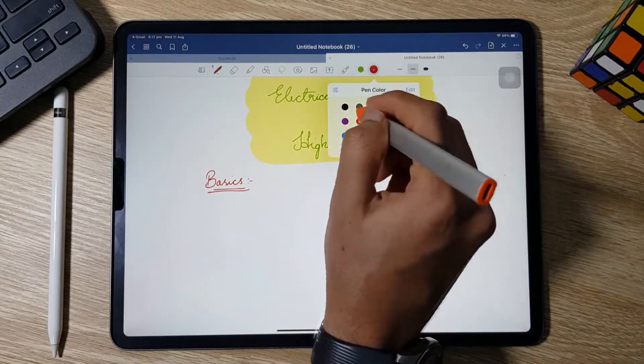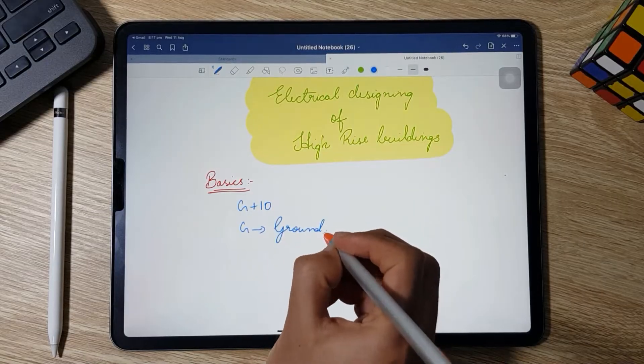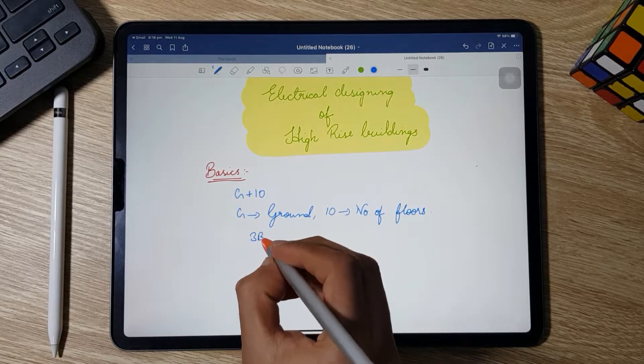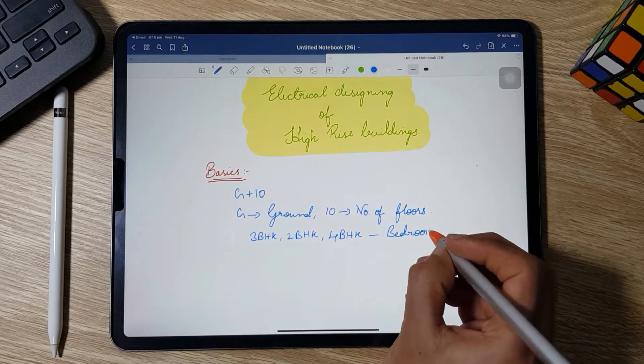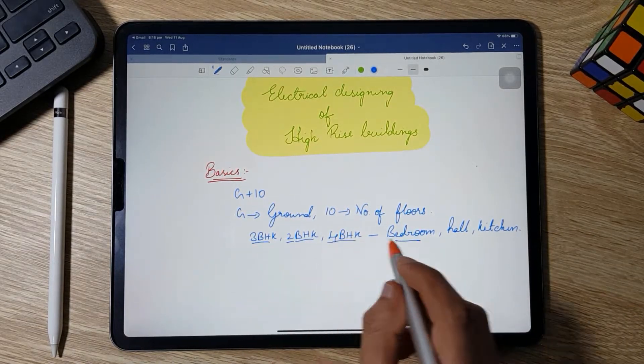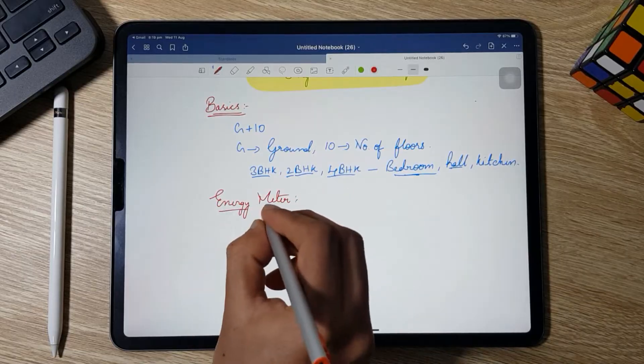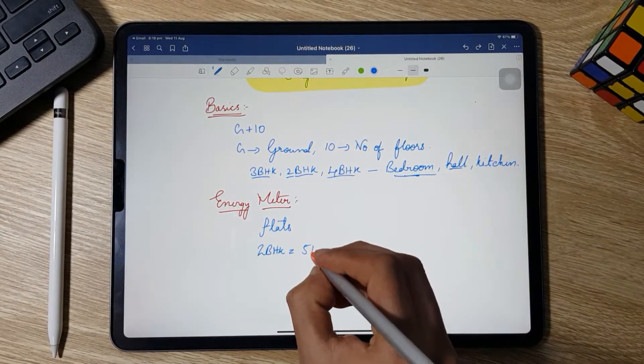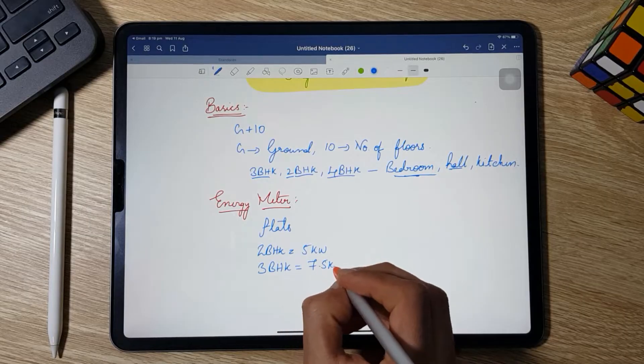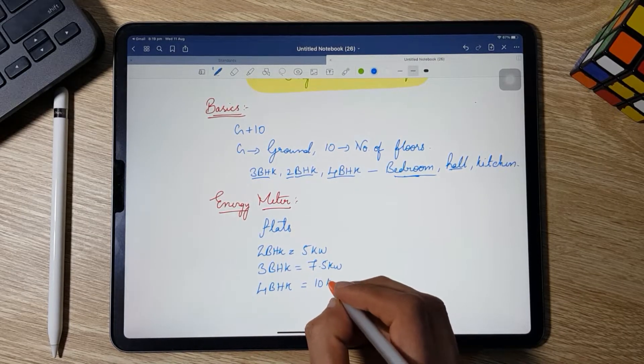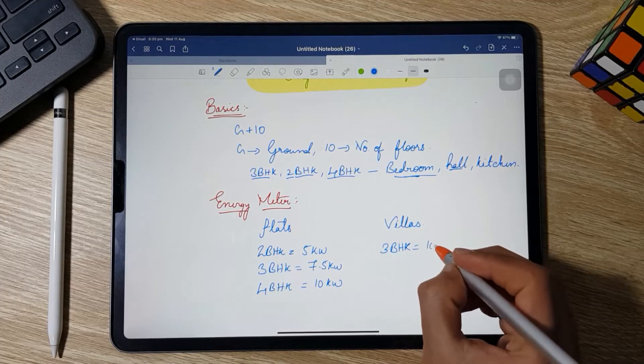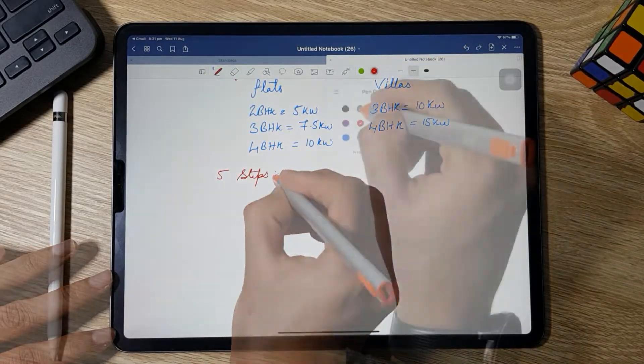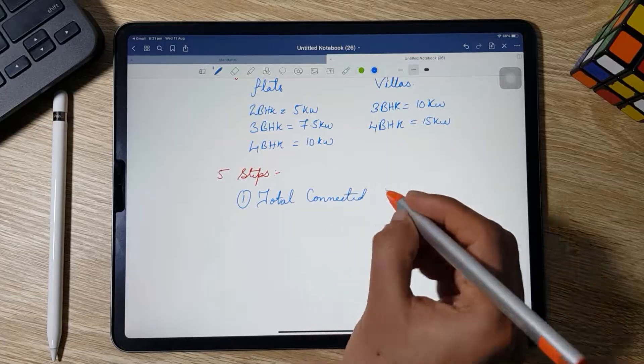First of all we need to go through some basics and standards before starting the design steps. In our case G+10 means ground plus 10 floors, which has multiple flat types: 2 BHK, 3 BHK, and 4 BHK — where BHK stands for Bedroom, Hall, and Kitchen. The energy meters used have government standards: for 2 BHK we use a 5 kW meter, for 3 BHK a 7.5 kW meter, and for 4 BHK a 10 kW meter. For villas, 3 BHK uses 10 kW and 4 BHK uses 15 kW.